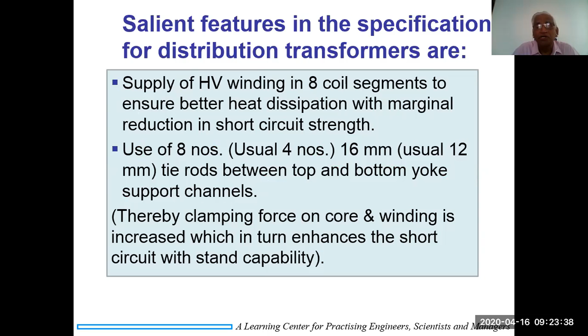Salient features and the specifications of distribution transformers are supply of HV winding in 8 coil segments to ensure better heat dissipation with marginal reduction in short circuit strength. Use of 8 numbers, usually 4 numbers, 16 millimeter, usually 12 millimeter tie rods between the top and the bottom yoke support channels. Thereby, clamping force on the core and the winding is increased, which in turn enhances the short circuit withstand capability.